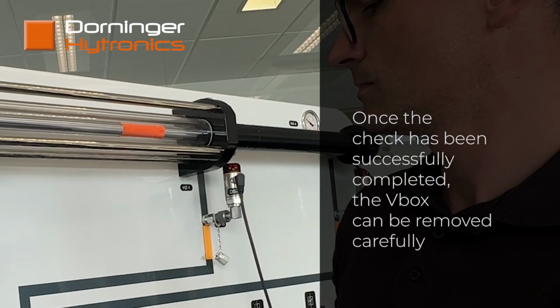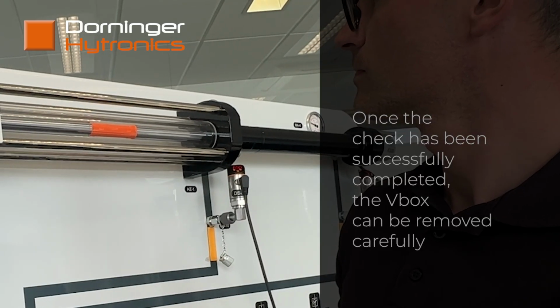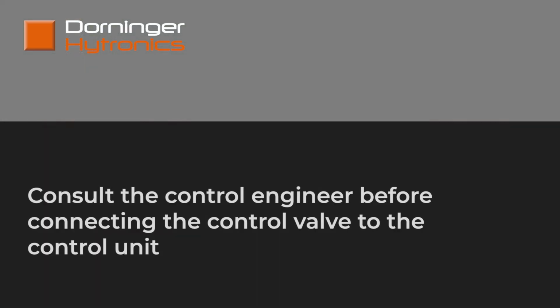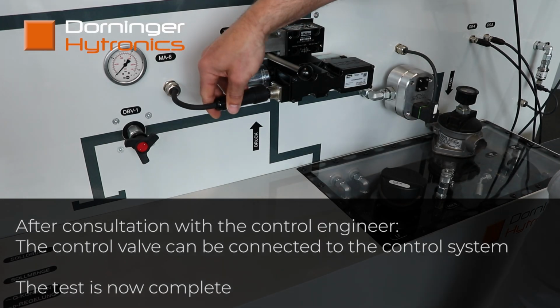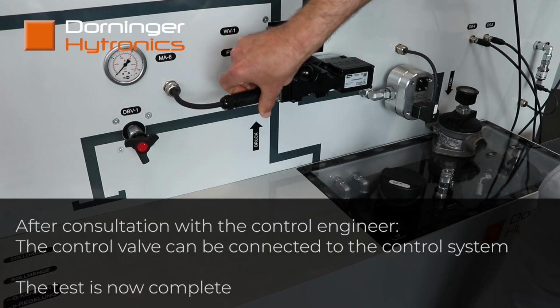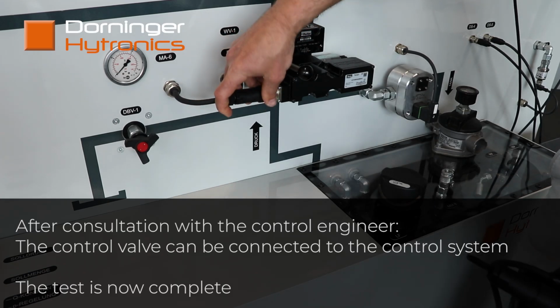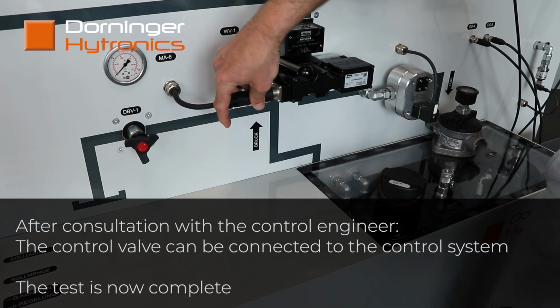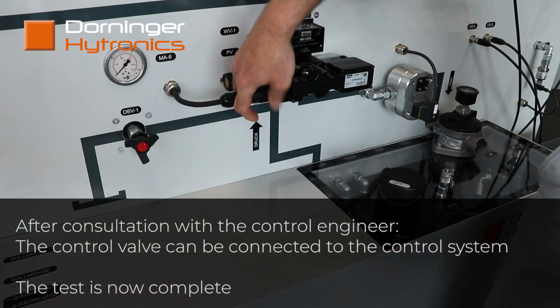After the test has been completed successfully, the Vbox can be removed. After consulting the control engineer or electrician, we then connect the valve connection cable to the control valve. The control cable connected directly to the control valve indicates that commissioning has been completed successfully. The test is now complete.